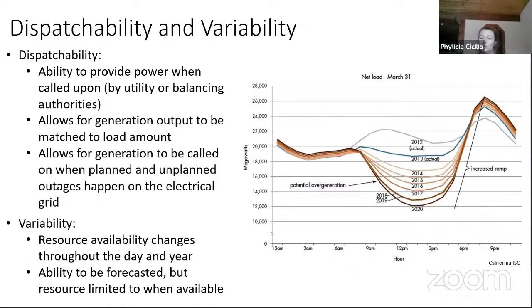That is the famous Californian duck curve. It shows from 2012 to 2020, the load as seen from the transmission system decreased to the lowest point in the middle of the day. That is from solar, specifically rooftop solar. It shows up here as a reduction of load because it's on the distribution system. From the perspective of the transmission system, the load is measured at the substation upstream of everyone's houses. Therefore, the rooftop solar generation is lumped all together with the load demand.